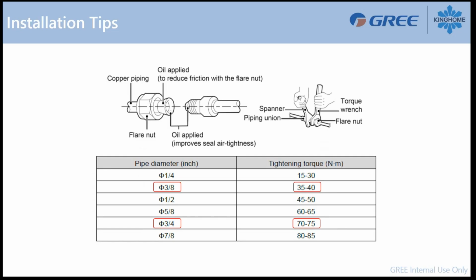So on the torque side, again, because we're using screw connections, we have only two pipe diameters that we will use. So the liquid line is always 3/8, and the suction line is always 3/4. Whatever the tonnage you are installing, this is always the pipe size we will use. So make sure you use your torque wrench when you do your connection and apply the right torque for each connection.